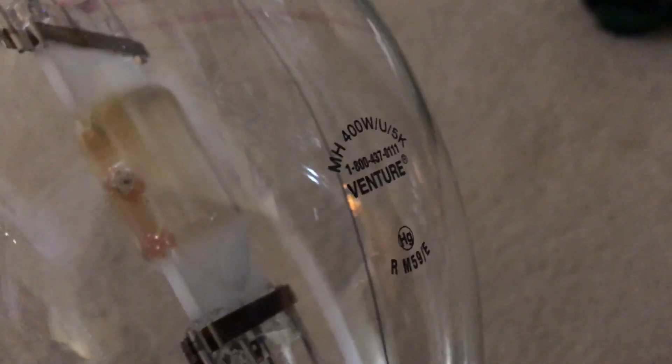The color temperature is 5000K or daylight according to the etching on the bulb. The lifetime on this bulb is only 15,000 hours if burned vertically, but 11,250 hours if burned horizontally. So you get more lifetime if you burn it base down or up — basically vertical. I also forgot to mention that we have a very nice hard aluminum base with a rough ceramic insulator, not polished.